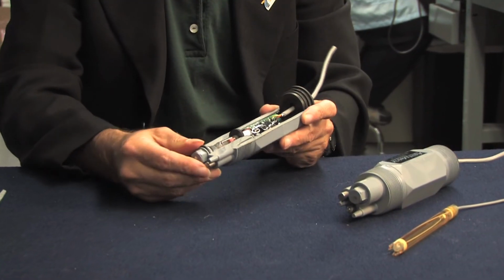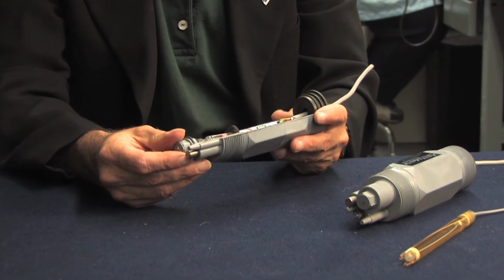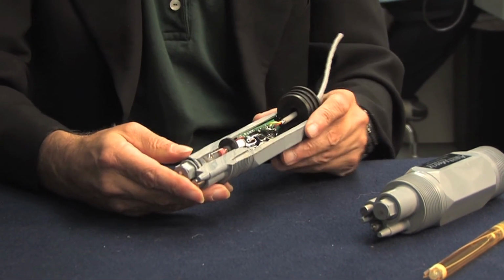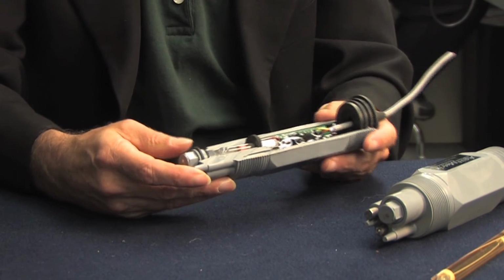Because we use a ground rod as a common to both circuits, any stray voltages that enter the solution are automatically canceled. The result is a very stable signal. By making the reference electrode a complete self-contained circuit, we now have access to the reference solution. All we need to do is unscrew the salt bridge, pour out the old reference solution, and pour in the new reference solution. The cost is less than $1.